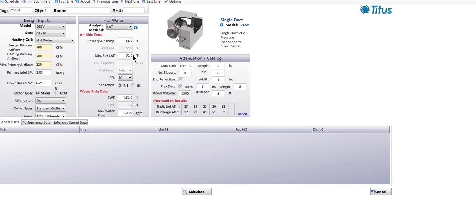You can tell if you've got a stratification problem in a room if you sit down and feel cold, then stand up and feel like you've got a fever — basically layers of air at different temperatures, leading to thermal comfort problems. So we definitely want to limit our leaving air temperature. Our program defaults to 95 degrees, which is the old ASHRAE guideline; if we go with the newer guideline, we probably don't want a leaving air temperature ever higher than 90 degrees.